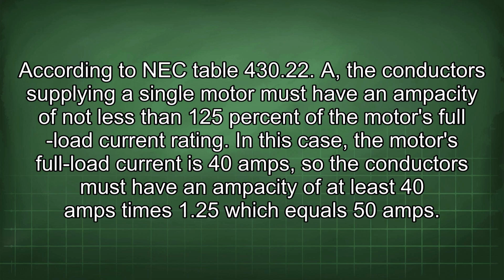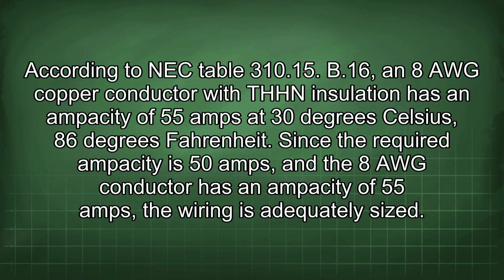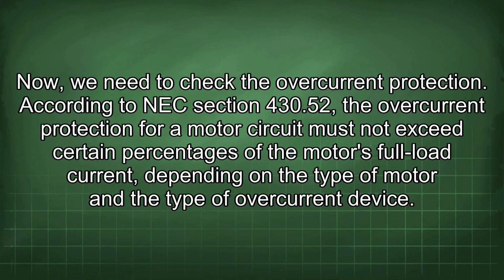full load current rating. In this case, the motor's full load current is 40 amps, so the conductors must have an ampacity of at least 40 amps times 1.25, which equals 50 amps. According to NEC Table 310.15(B)(16), an 8 AWG copper conductor with THHN insulation has an ampacity of 55 amps at 30 degrees Celsius, 86 degrees Fahrenheit. Since the required ampacity is 50 amps, and the 8 AWG conductor has an ampacity of 55 amps, the wiring is adequately sized. Now, we need to check the overcurrent protection.